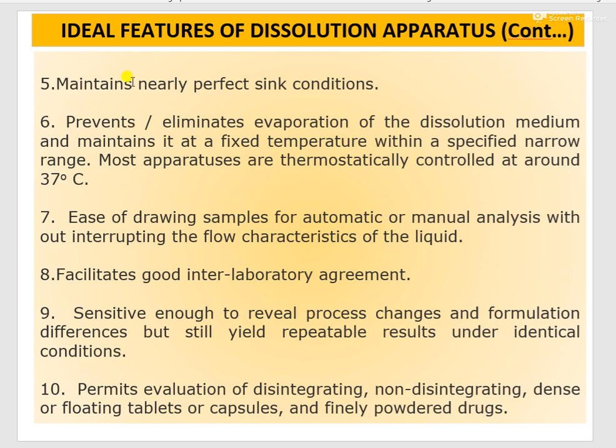The dissolution apparatus should maintain nearly perfect sink conditions. It should prevent or eliminate evaporation of dissolution medium and temperature should be controlled. Most apparatus are thermostatically controlled at around 37 degrees. The sample should be easily drawn without interrupting the flow characteristics of the medium. It should provide good inter-laboratory agreement. The dissolution apparatus should be sensitive enough to reveal process changes and formulation differences, yet still yield repeatable results under identical conditions.